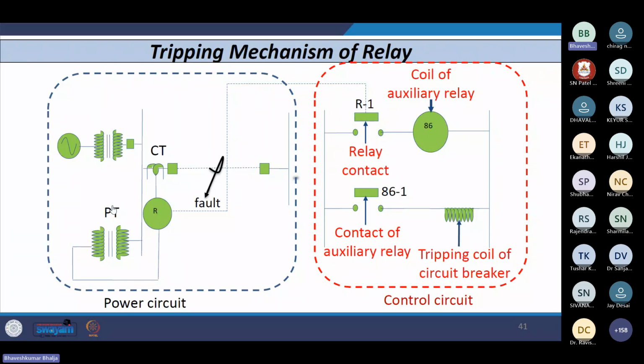Anyway, we are not going into that detail. So your circuit breaker becomes open. Then, whenever the breaker becomes open, the dielectric strength of the SF6 gas is already utilized. So we have studied, right? If you have studied high voltage engineering, what is the nature of the gaseous medium? It is going to regain its dielectric strength, but you have to wait for some time, so that it is ready for the next operation. That time is nothing but your reclaim time, right?